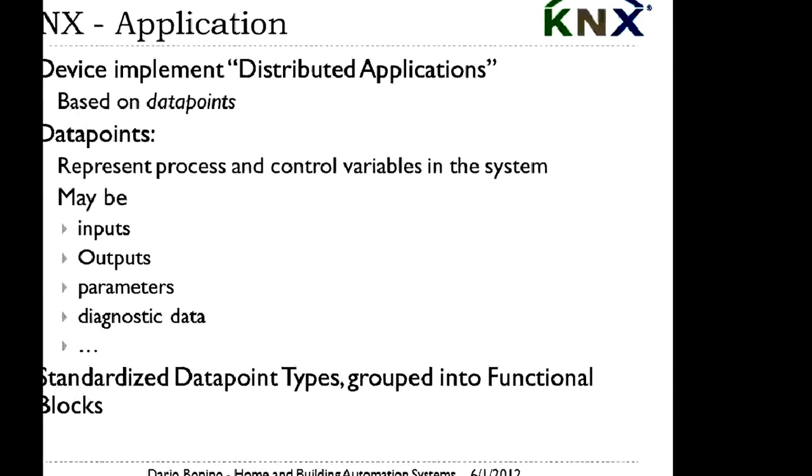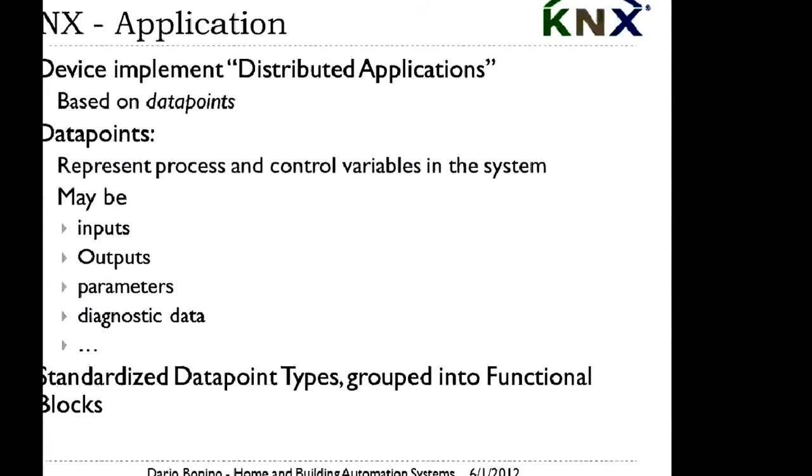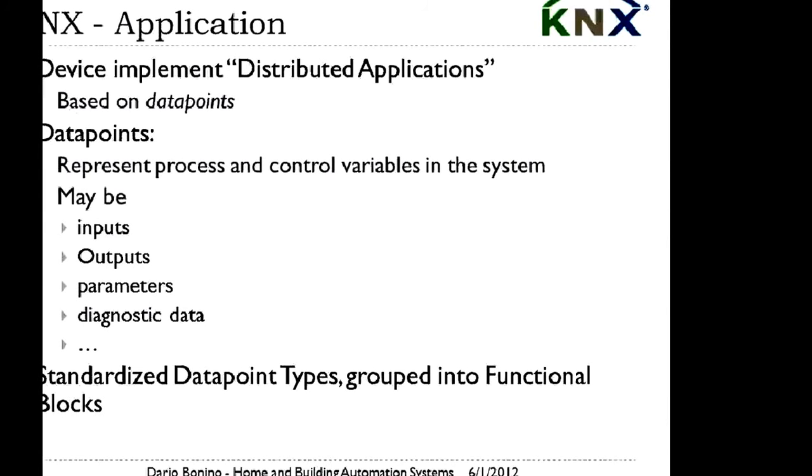Every physical device has software running on it, which exposes a set of data points. Data points can either be inputs, something that the device expects from the outside; outputs, something that can be sent by the device; some parameters for changing the device behavior; or some diagnostic data on the device. So we have these data points, and we program the application by connecting the data points together.